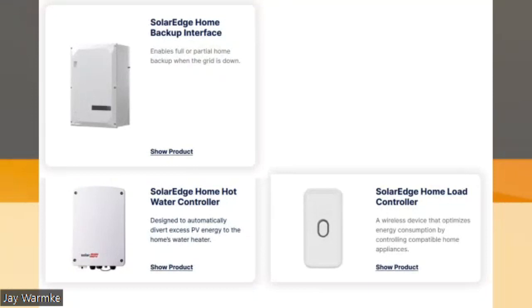I mentioned another load dump here is the hot water controller. Once again, instead of sending power back to the grid, you use your system's excess energy to heat your hot water. This process has been used in standalone systems a lot, where the hot water heater serves as a load dump. Here, you just set it up so that during the day excess energy is directed to your hot water heater instead of the grid, where you might otherwise be paying retail rates to heat your water.